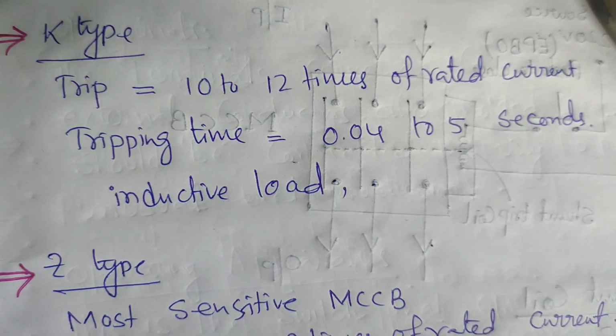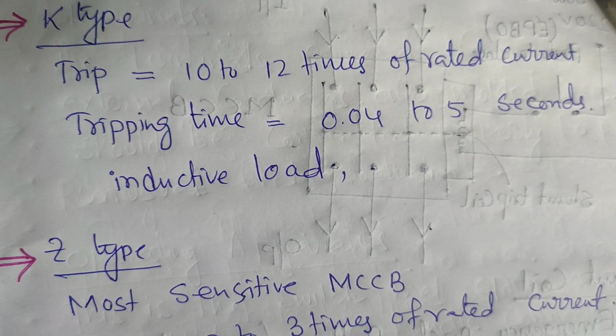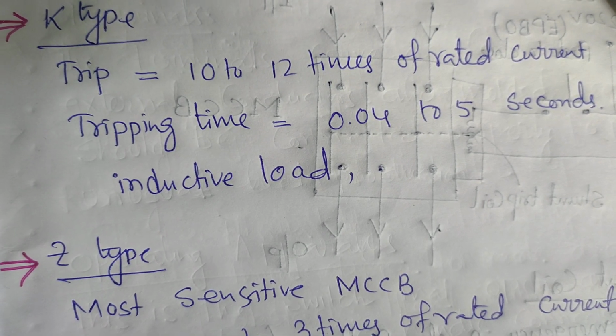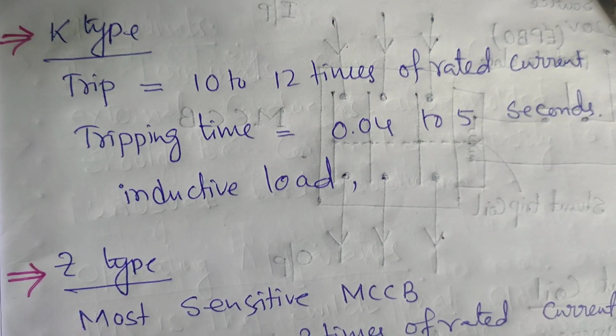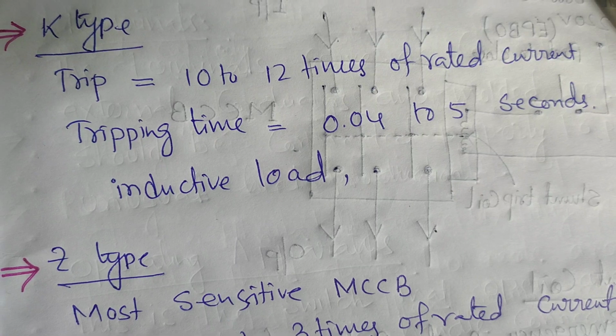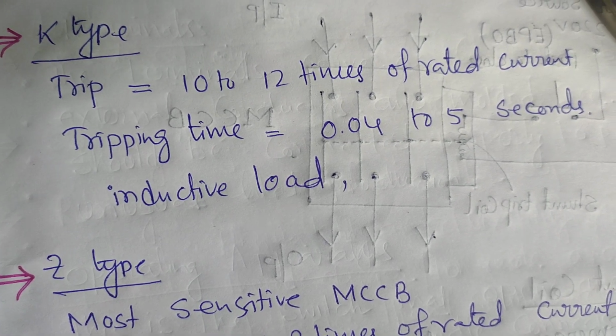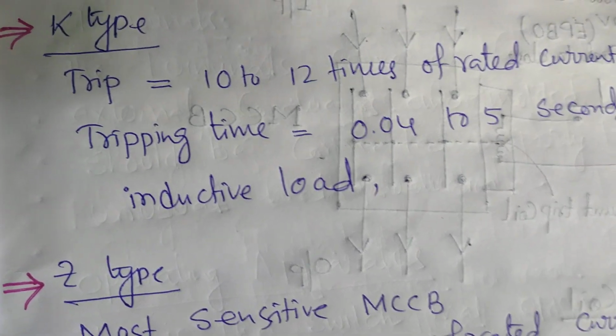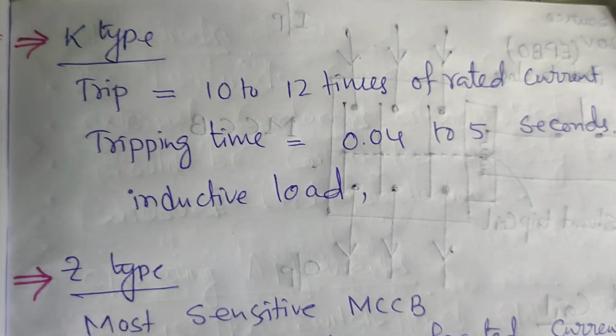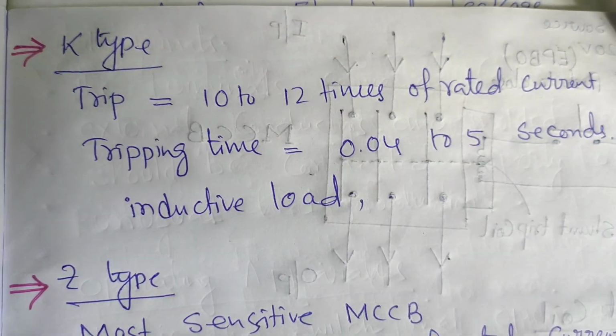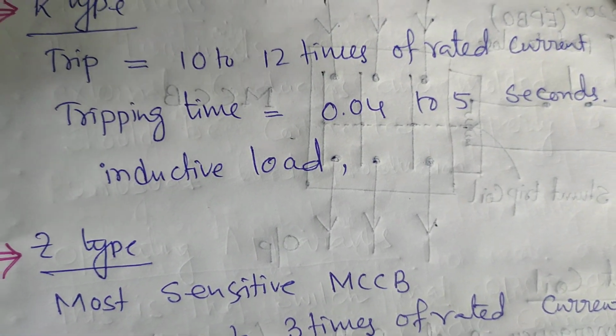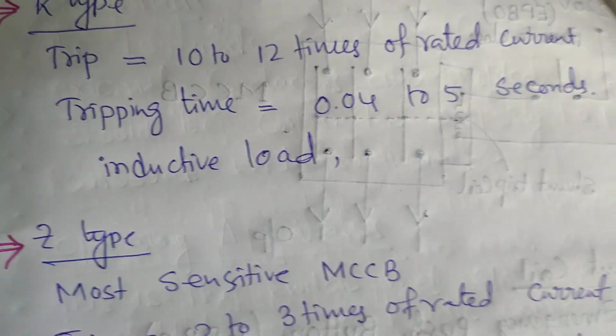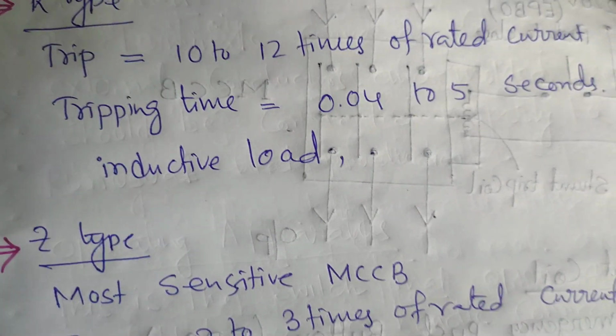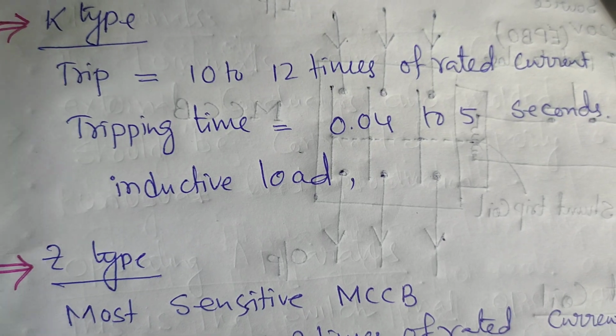K type MCCB. For the K type, the rated current multiple is around 10 to 12 times, and the tripping time is 0.04 to 5 seconds. Within 5 seconds, that circuit should operate. So for an inductive load circuit with these features, we have to use the K type MCCB.